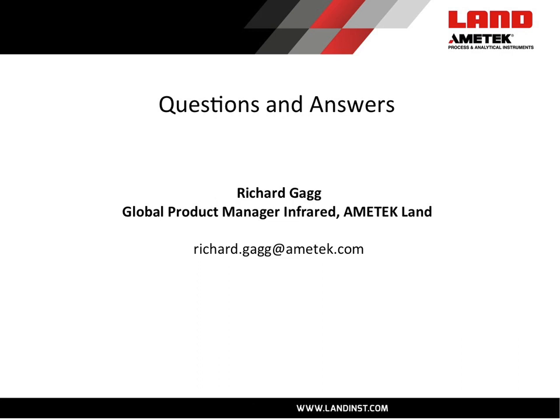As a follow-up, a questioner asks for additional information on this subject. If you email richard.gag@amatech.com after this session and put in your question, I can arrange to get you more materials. Here's the next question: what is the average accuracy of pyrometers? The typical measurement uncertainty depends on the model, but it's typically very accurate — between 0.25 and 0.4 percent of the pyrometer's reading. As a follow-up: which range of temperature can they measure? We can measure below zero Celsius up to over 3000 Celsius — you just select the model for your particular application.